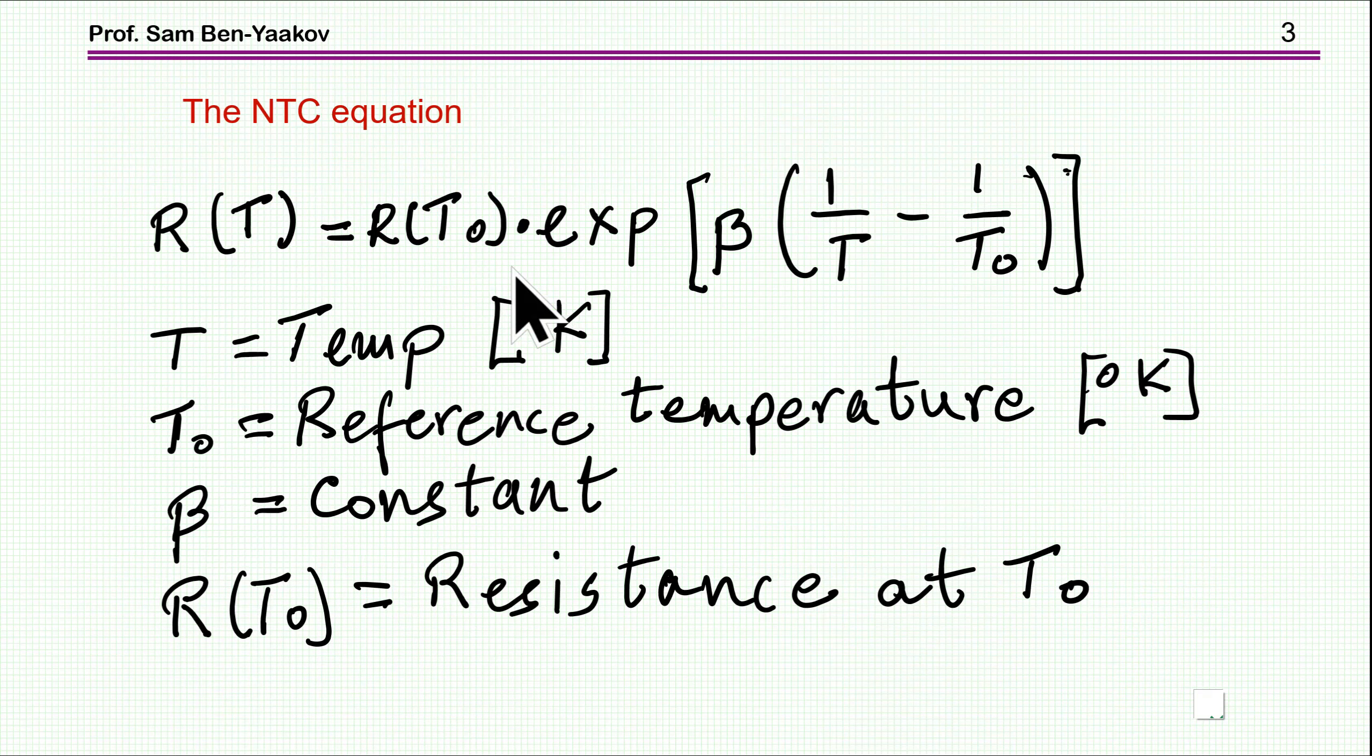There are many ways to describe the behavior of a thermistor by an experimental equation. One of them is this exponential type equation, which I personally like very much. It has been shown that it fits very well in many commercial units. The way it goes is the resistance at a given temperature is equal to the resistance at a reference temperature, and then e to the power of beta. Beta is a constant, it's about 4,000, 3,000, that's the range. And here we have 1 over T, which is the temperature that we are looking for, and the reference temperature. It's important to note that all these temperatures are in Kelvin. So you have to add something like 273 degrees if you are working in degrees Celsius.